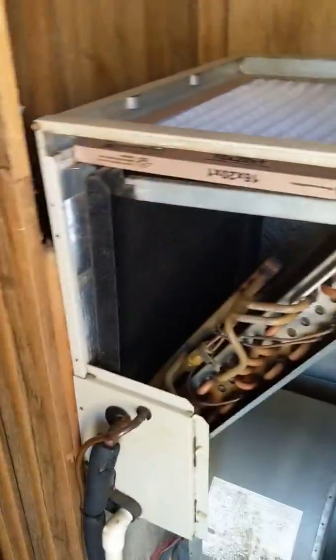This unit never turned off — the fan just stayed on. It was on auto; it's supposed to turn off after a couple of minutes, but it just never turns off, even to this moment. I know the condenser outside is turning on. Pretty sure we can go out there and listen to it once I repeat the steps here.